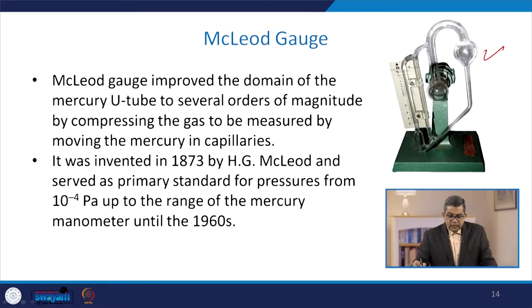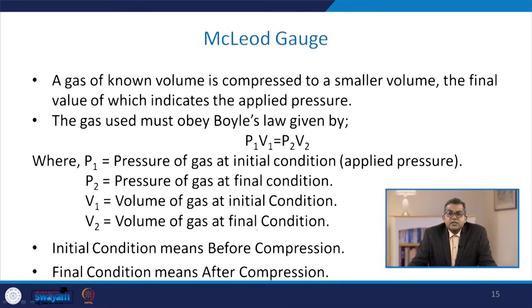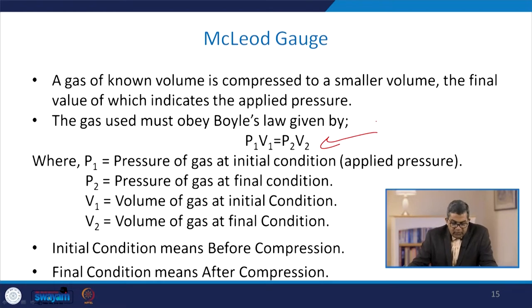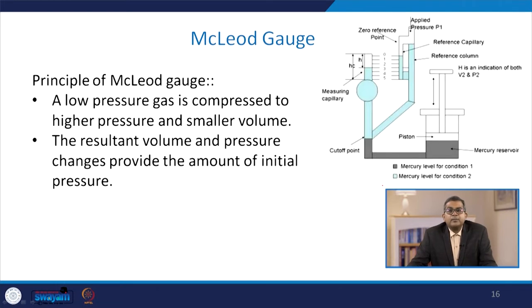The McLeod gauge improved the domain of the mercury U-tube manometer by several orders of magnitude by compressing the gas to be measured by moving mercury in capillaries. Invented in 1873 by H.G. McLeod, it served as a primary standard for pressure from 10⁻⁴ Pascal up to the range of mercury manometers until the 1960s. A gas of known volume is compressed to a small volume, the final value of which indicates the applied pressure; the gas must obey Boyle's law: P₁V₁ = P₂V₂.